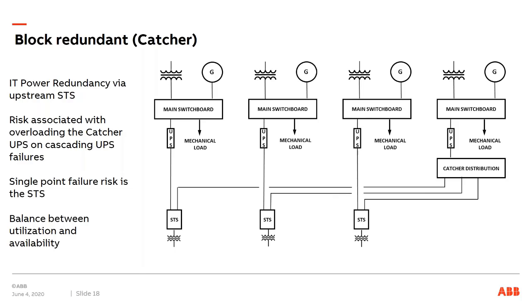Compared to the other one, this one is fairly easy to handle because the load is supported by each main UPS, and as load is added, the UPS will tell you if it's overloaded. The concern that some people have with this is that the catcher UPS is sitting idle. It's running, but it's not doing anything. And then if something happens, it has to take a full, typically 100% load step. But it's a very popular configuration. We see a lot of those.